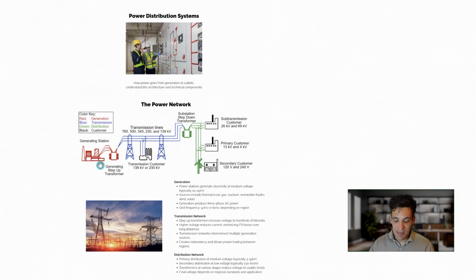Well, power is generated at generators. So we might have a coal power station, we could have a nuclear power station, we could have gas engines, we could have renewable energy facilities. These are sources which generally produce power at something like 10 to 25 kilovolts, depending on the specific source, and then we'll connect to a step-up transformer. So a step-up transformer will take this 10,000 volts or 25,000 volts, whatever the generator is producing, and step it up to transmission lines. So transmission lines operate at higher voltages. Again, we spoke about in the last section that this is essential because it ensures we have minimal power losses when transmitting power long distances. Our solar farm might be 5 hours away from a city, so we need a way of moving that power efficiently without losing too much of it to where the power is actually being used. So that's done through transmission lines, which could step up the voltage to 500,000 volts, 345,000 volts, 138,000 volts.